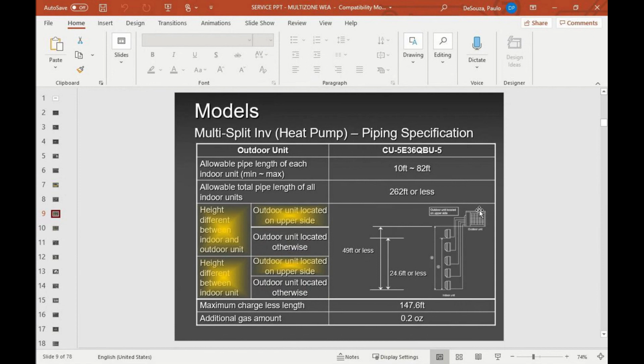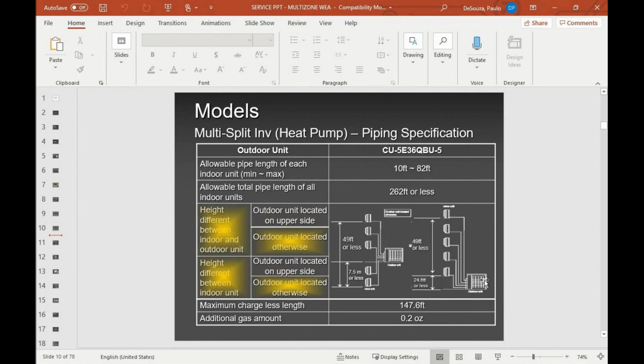Okay, guys. Slide 9. I was talking to you about height limitations. Make sure you have the correct height difference between outdoor and indoor, between indoor and outdoor, between the first indoor to the last indoor unit. All height difference you have to pay attention to. Why? Because of oil return, guys. We need oil return freely and smoothly to save that compressor from burning out prematurely. Okay, guys? So our compressors can last for more than 10 years, no problem. So make sure you take care of it. Make sure you respect all this length, these pipe length differences and all that stuff. Once you cross 147 feet, you need to add refrigerant, guys.